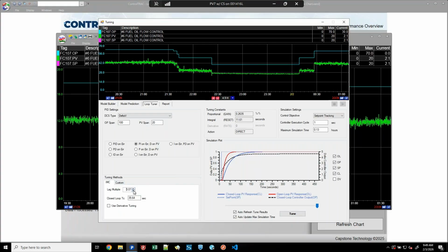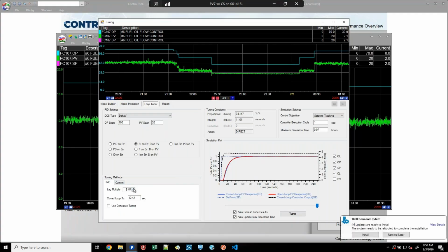And then what I would do is I would try to speed this up as much as possible before causing any overshoot. So I'm going to keep an eye on my actuator, that black line, and the blue line, the closed loop response. So at a lambda of 3, we're stable. Let's back off on that and try to speed it up, maybe around a lambda of 1.5. If we go any faster than 1.5, we're starting to see overshoot in our actuator. So there's no need to kick this actuator. I don't need to settle that quick. I don't want to introduce any aggressive tuning to my control loop. So I'm going to back off just a little bit. So I would tune this maybe around a lambda of 1.5, a lambda of 2. I think that's a safe spot to tune this loop here.